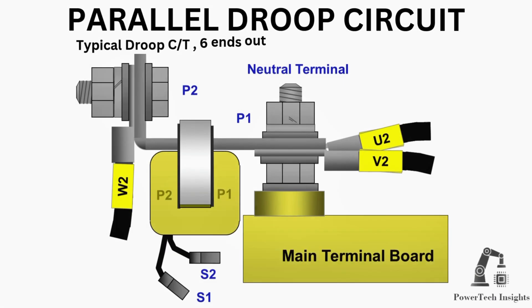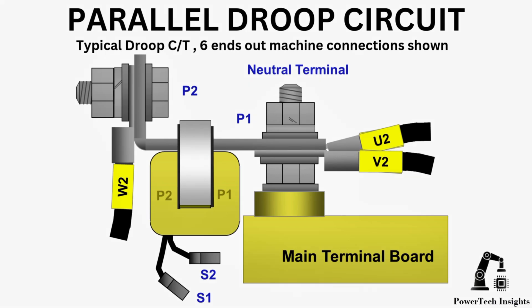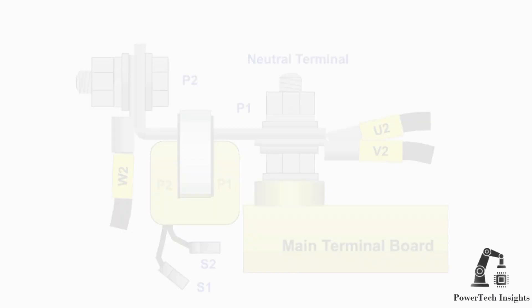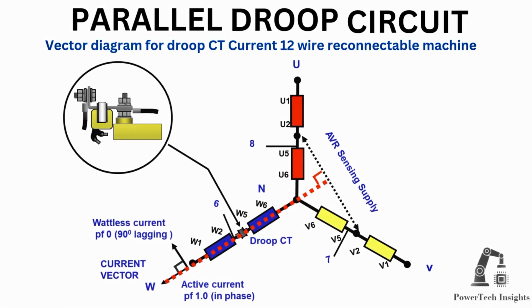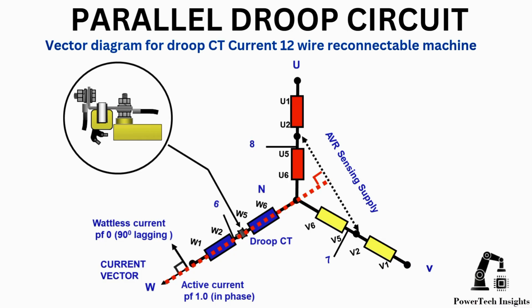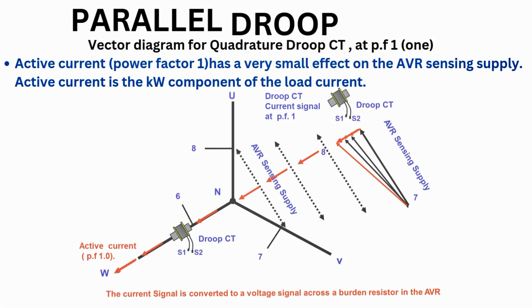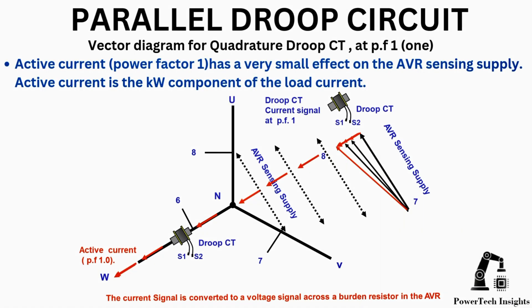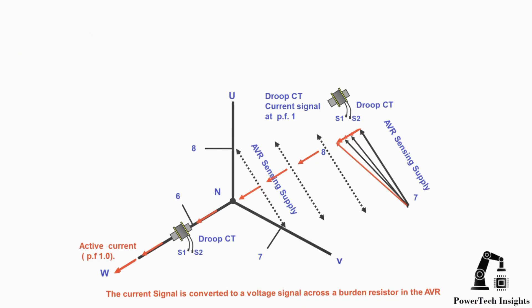This picture shows a typical droop CT 6-ends-out machine. This is the vector diagram for droop CT current on a 12-wire reconnectable machine. This is the vector diagram for quadrature droop CT at power factor 1. Active current at power factor 1 has a very small effect on the AVR sensing supply. Active current is the kilowatt component of the load current.